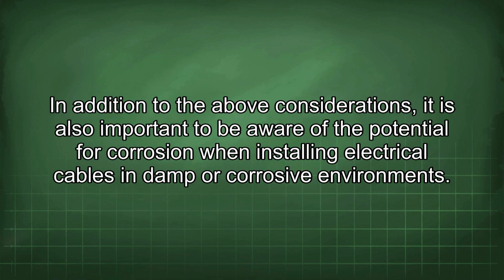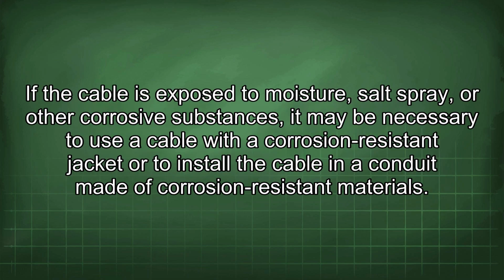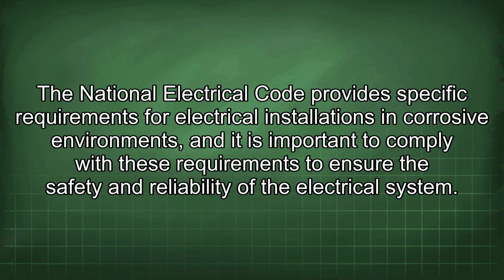In addition to the above considerations, it is also important to be aware of the potential for corrosion when installing electrical cables in damp or corrosive environments. If the cable is exposed to moisture, salt spray, or other corrosive substances, it may be necessary to use a cable with a corrosion-resistant jacket or to install the cable in a conduit made of corrosion-resistant materials. The National Electrical Code provides specific requirements for electrical installations in corrosive environments, and it is important to comply with these requirements to ensure the safety and reliability of the electrical system.